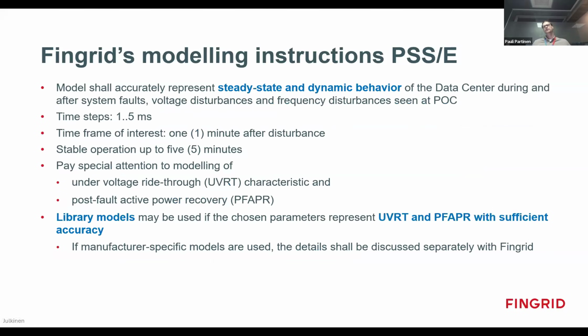For the PSS/E, the approach is a bit different. We also expect that the basic steady state and dynamic behavior of the plant is represented, but we do not require vendor-specific models, at least at the moment, because what we see is that the modeling on the PSS/E side is not there yet. You can use PSS/E library models, but special attention must be given to modeling of undervoltage ride-through and post-fault active power recovery.